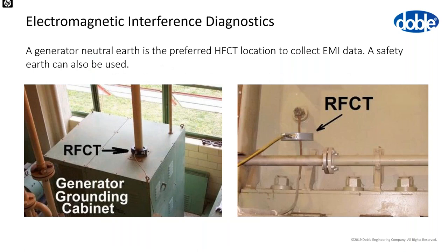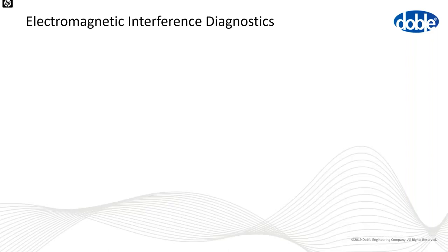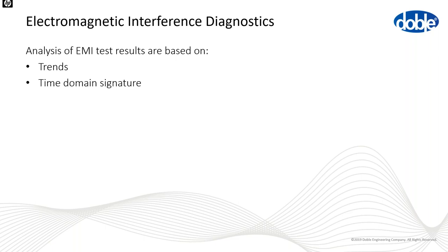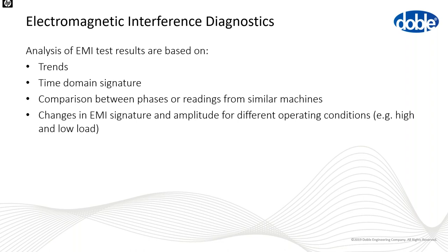For generators, we typically prefer the neutral earth for HFCT placement, but we can also use a safety earth or previously installed passive couplers depending on site conditions. For motors, we typically clamp onto a power cable or power conduit, or a safety earth if neither is available. Analysis of EMI test results is typically based on trends over time, time-domain signature shape, comparisons between phases or similar machines, and changes in signature with different operating conditions.